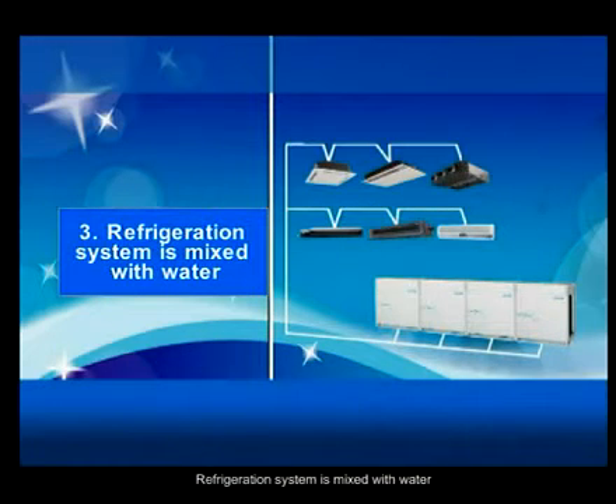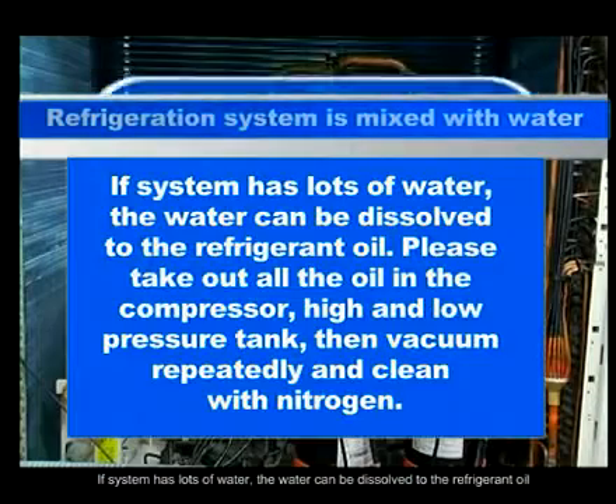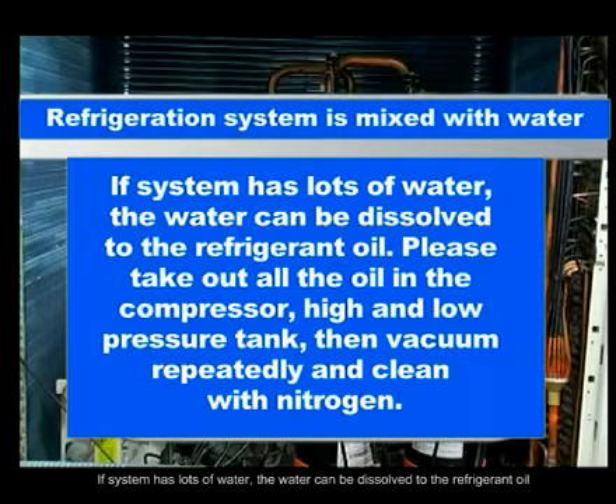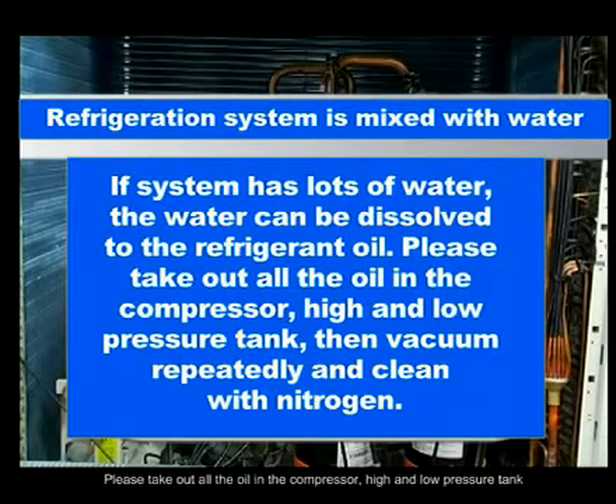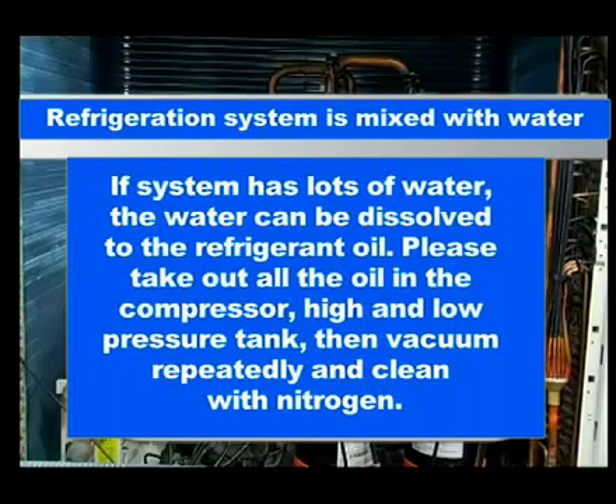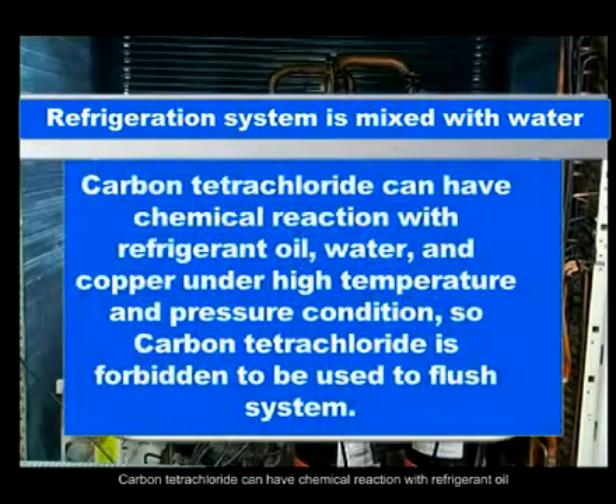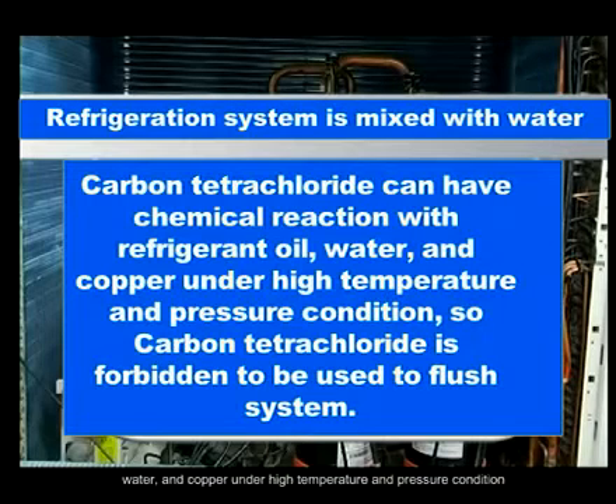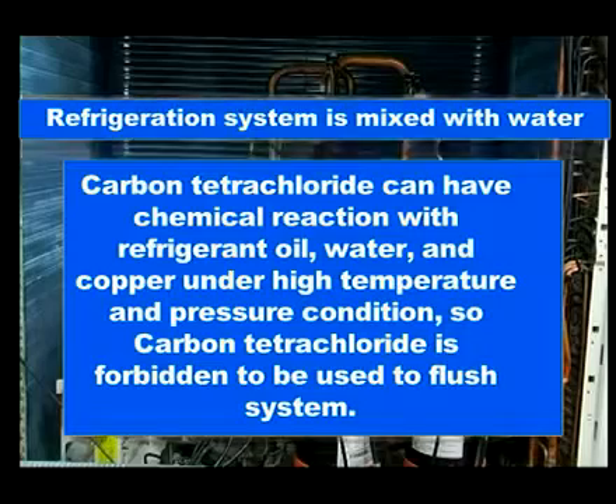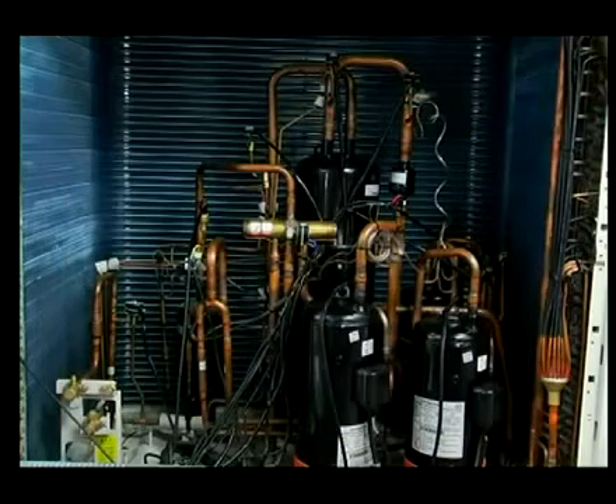Refrigeration system is mixed with water. If the system has lots of water, the water can dissolve into the refrigerant oil. Please take out all the oil in the compressor and the high and low pressure tank, then vacuum repeatedly and clean with nitrogen. Carbon tetrachloride can have a chemical reaction with refrigerant oil, water, and copper under high temperature and pressure conditions, so carbon tetrachloride is forbidden to be used to flush the system. Repair instructions when the system is mixed with water.